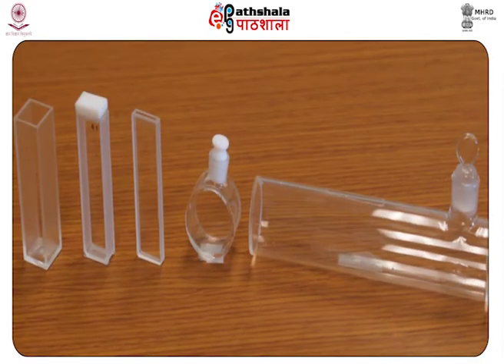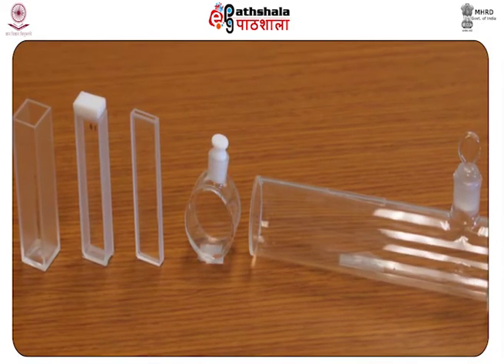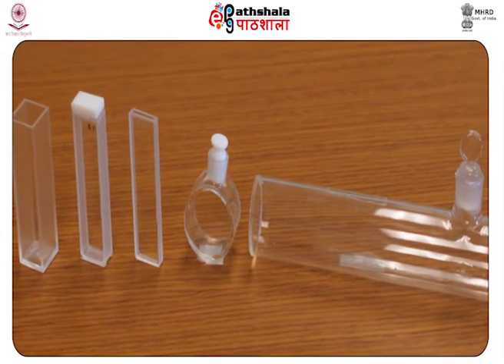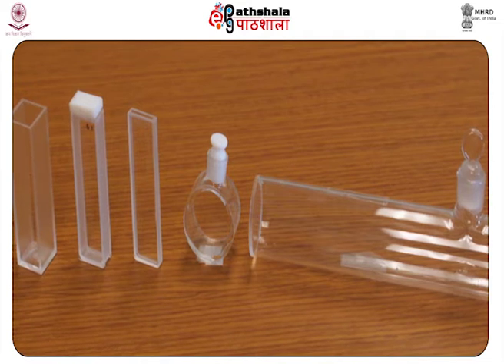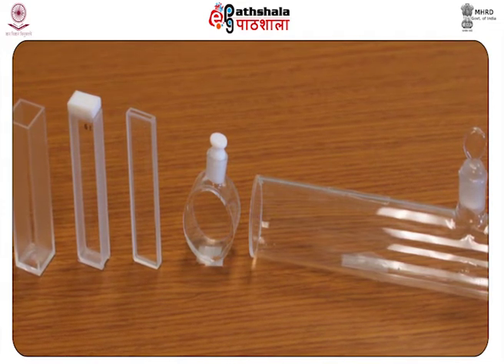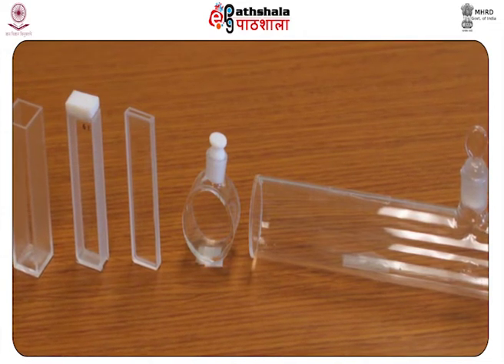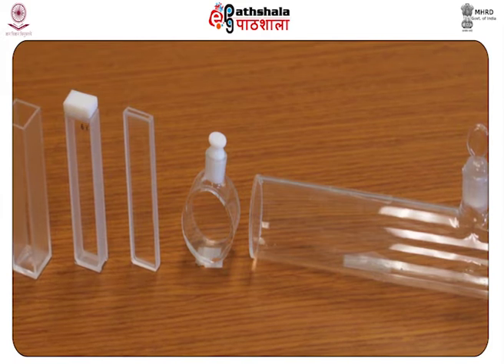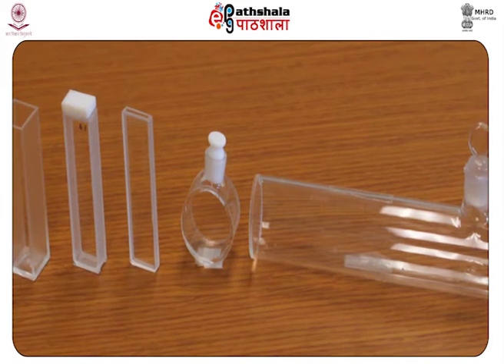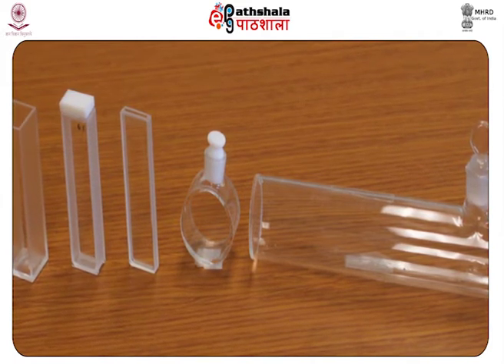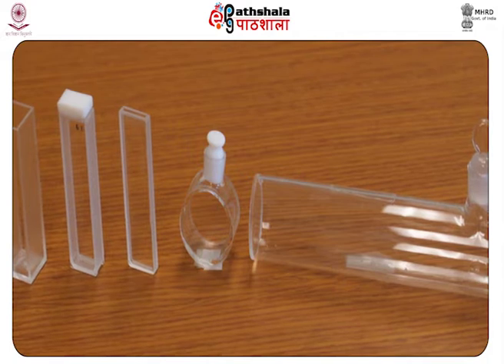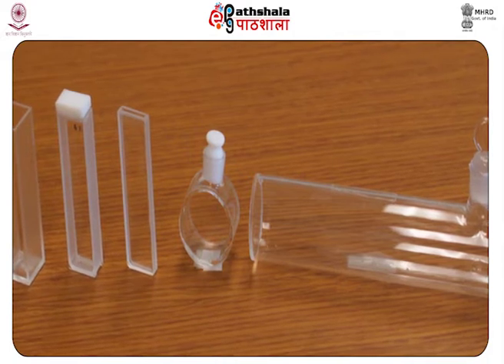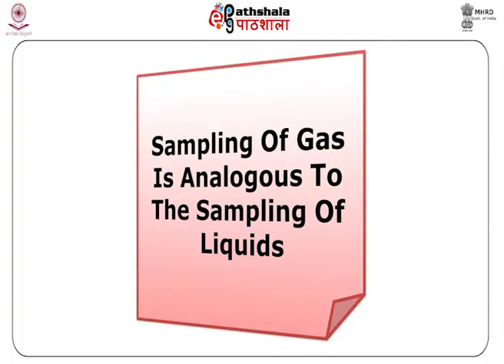Liquid samples are kept in cells made of alkali halides. Aqueous solvents are not used because they will dissolve the alkali halides in the cell, and hence only organic solvents like chloroform are used. Next is gas. Sampling of gas is analogous to the sampling of liquids.